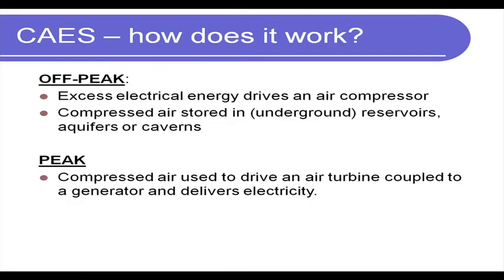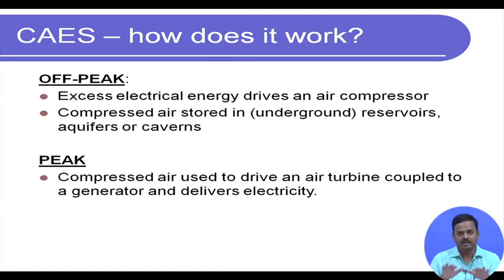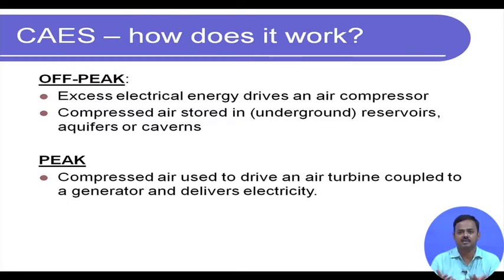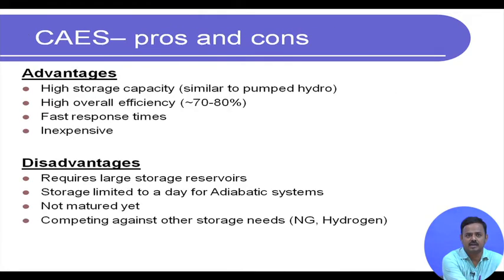To summarize how CAES works: electrical energy during off-peak hours drives an air compressor and the compressed air is stored in underground reservoirs — typically abandoned salt mines are very good candidates. During peak hours, the compressed air drives an air turbine coupled to a generator and generates additional electricity.